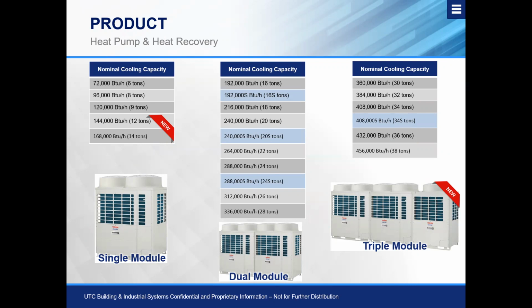For a dual module, or beginning with a twin kit, will range from 16 all the way to 28 tons. Now you'll see on the 16, 20, and 24 ton machines, we have an S in the module. That S is for a space saving configuration. For example, for a 16 ton space saving unit, an 8 is typically what we use, so we're taking 2 units and putting them together. Well, instead of using an 8 ton unit and an 8 ton unit, we may use a 10 ton unit and a 6 ton unit to take up less physical footprint if we're dealing with an application that has limitations as far as the area we can put the unit in.